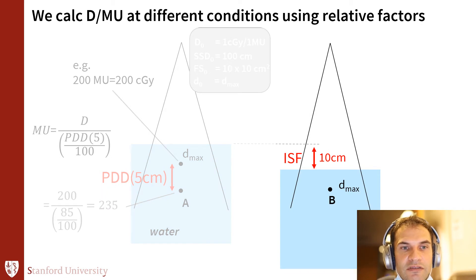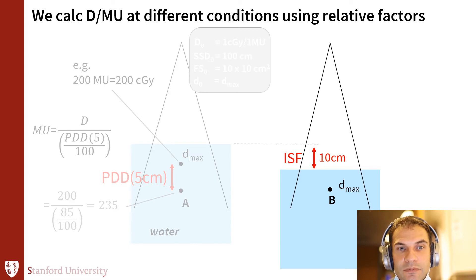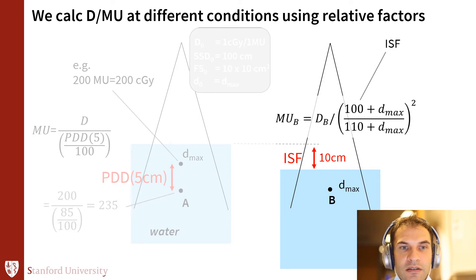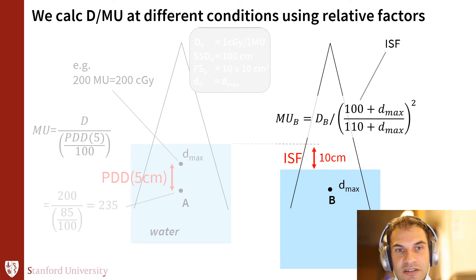A different scenario is if you want to move the phantom down — keeping the depth the same, still at D-max, but now using SSD 110. For that, you need to change the inverse square factor, going from SSD 100 to SSD 110.